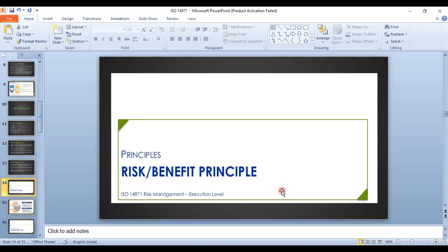Finally, they will calculate the risk benefit profile. Based upon that, they clearly calculate this risk benefit value. Based upon that value, they can decide whether the medical device should be recalled or not, or whether some other risk management plan has to be implemented or not. Everything they can take the decision on. That is the risk management principle. I think you people have cleared the understanding of the risk benefit principle.